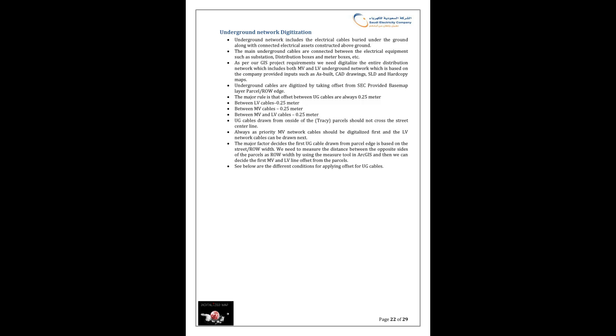Underground cables are digitized by taking offset from the SEC provided base map layer, parcel ROW edge. The major rule is that the offset between UG cables is always 0.25 meter. Between LV cables, 0.25 meter. Between MV cables, 0.25 meter. Between MV and LV cables, 0.25 meter. UG cables drawn from the side of the parcels should not cross the street.